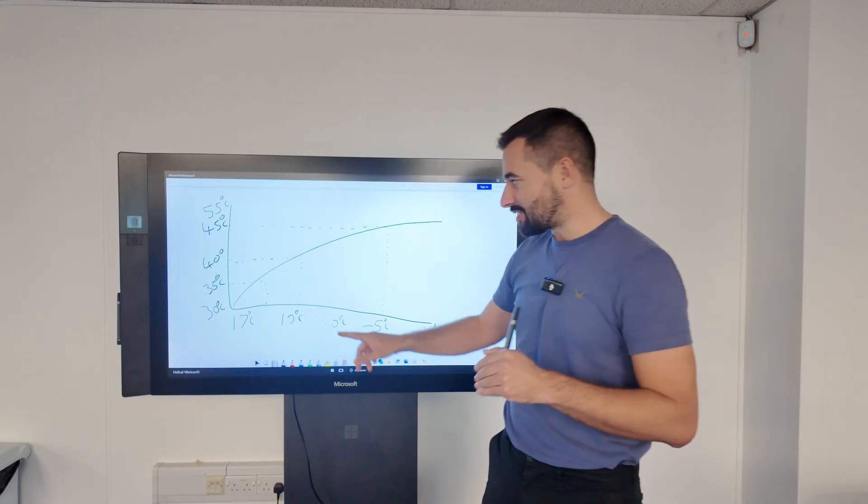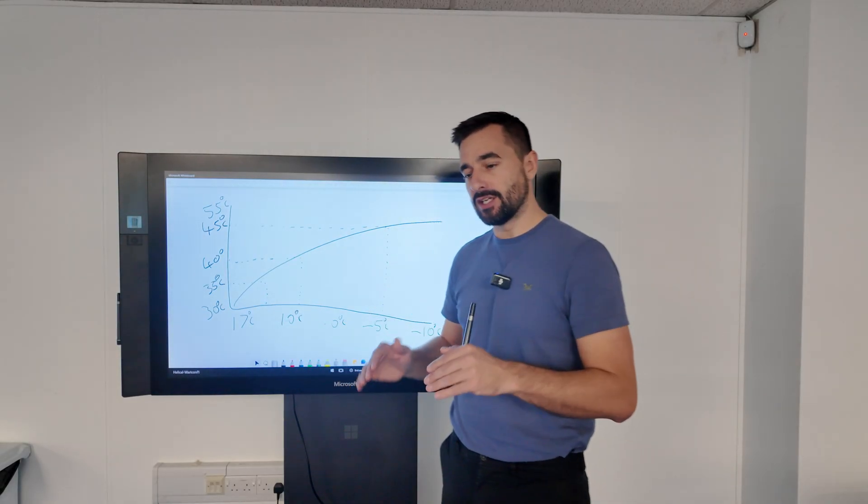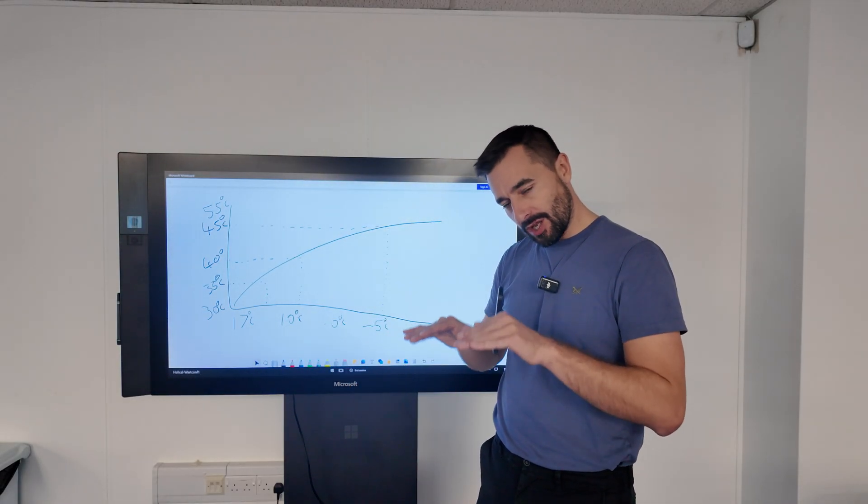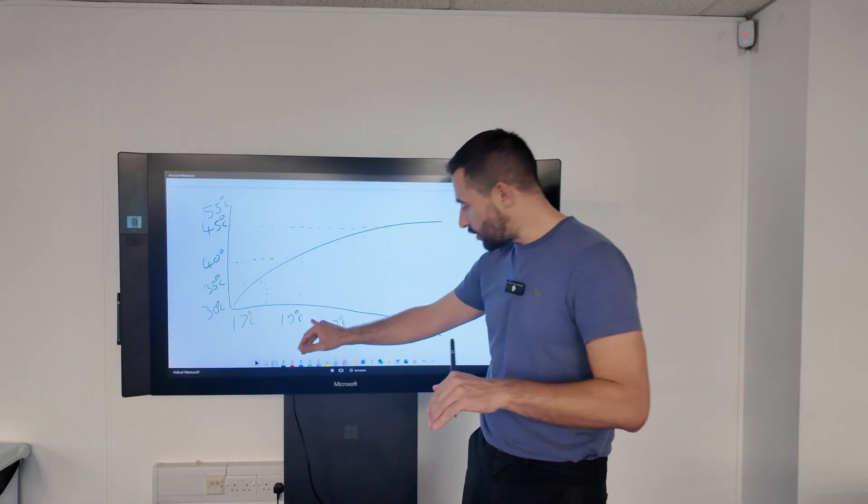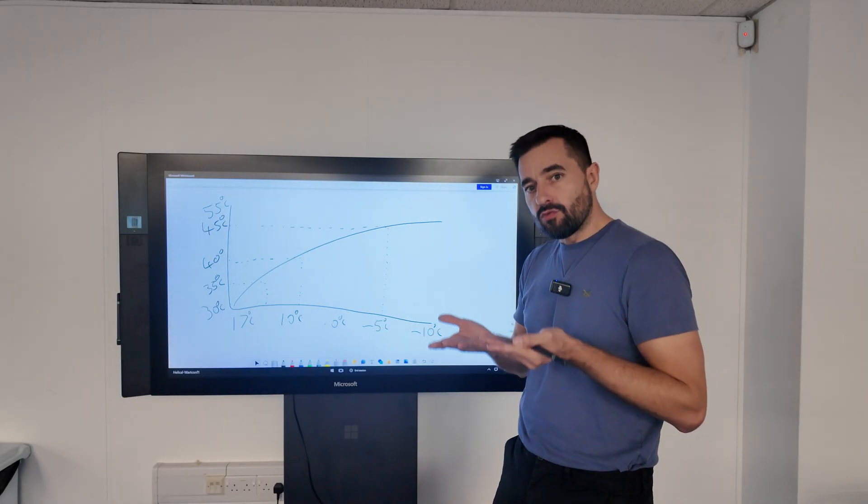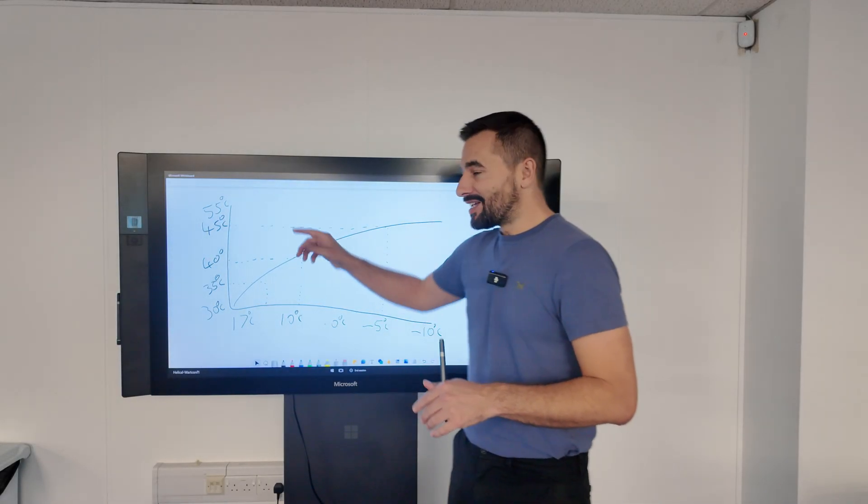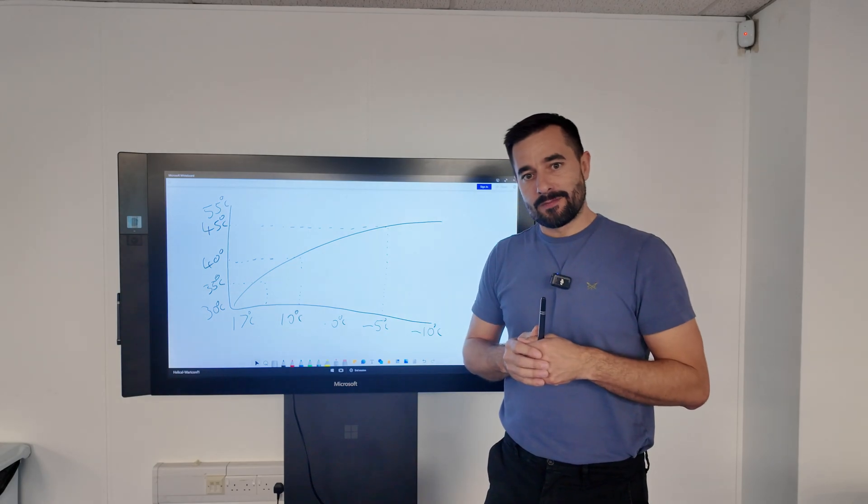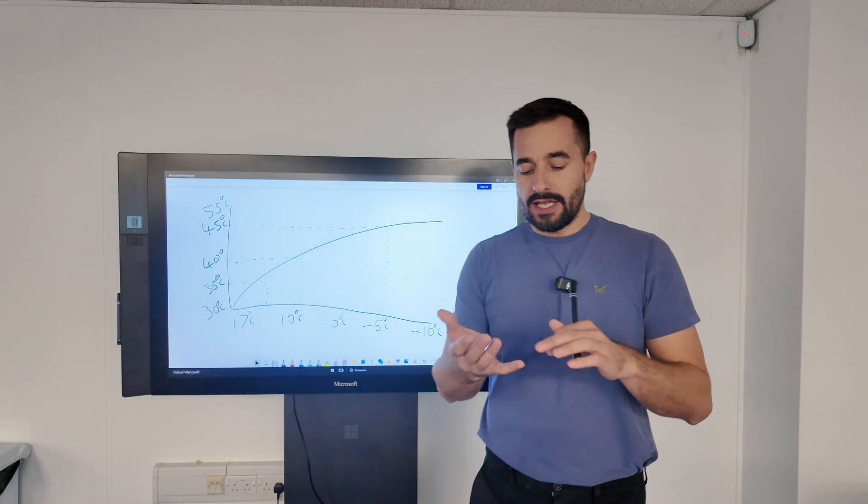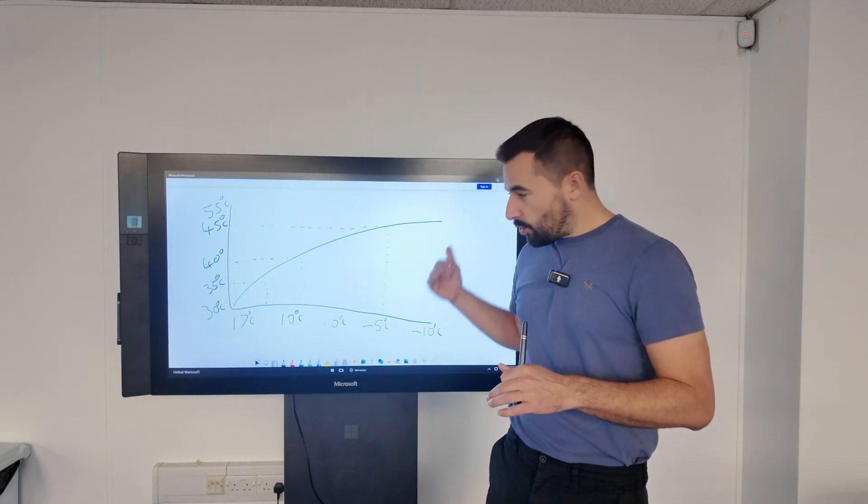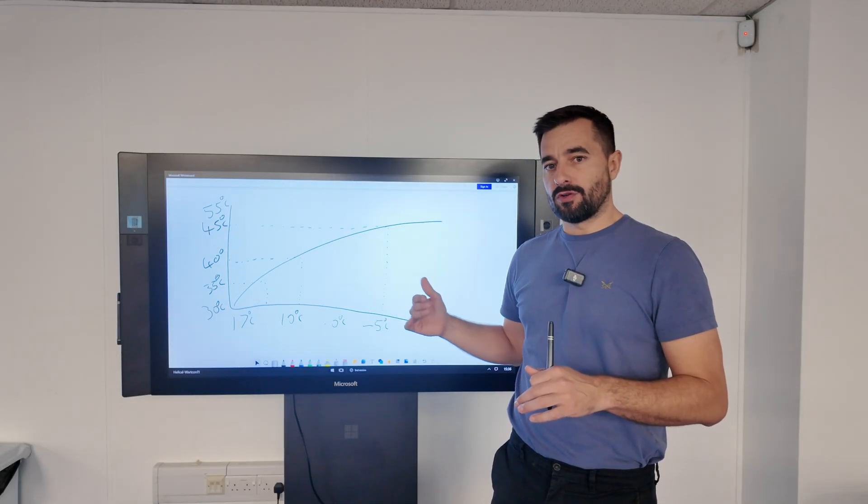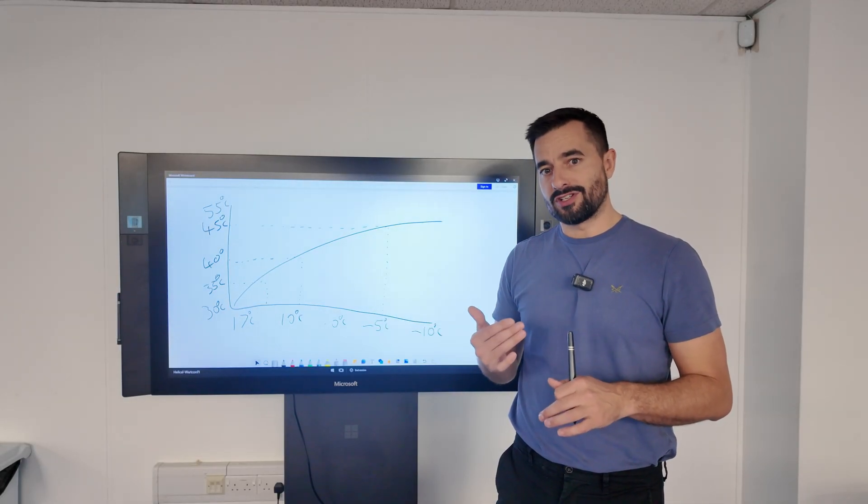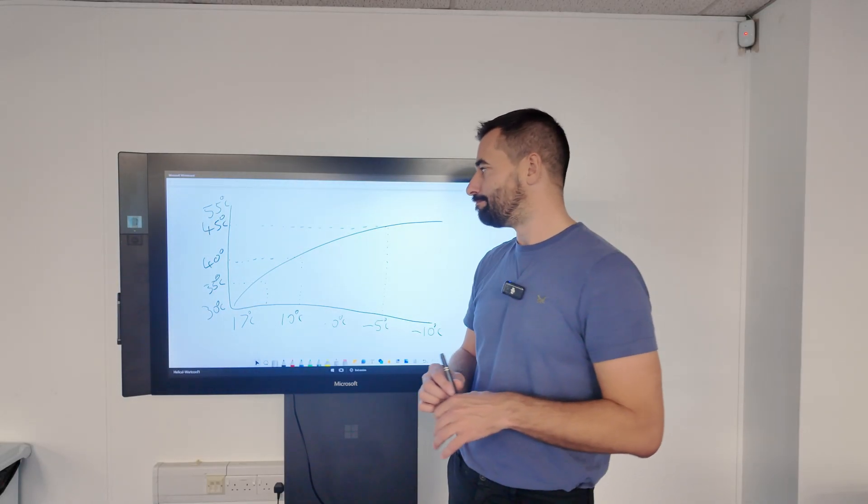Think back to that heat loss calculation and that degrees and watts per degree rise. The warmer it is outside, the less heat we need, so we can lower the flow temp, lower the heat flow into the house. The cooler it gets outside, we can raise the flow temp and increase the watts going into the house. It's worth you guys, be it a homeowner or an installer, just working your way back through the information I've told you, just to absorb it so you truly understand weather compensation.